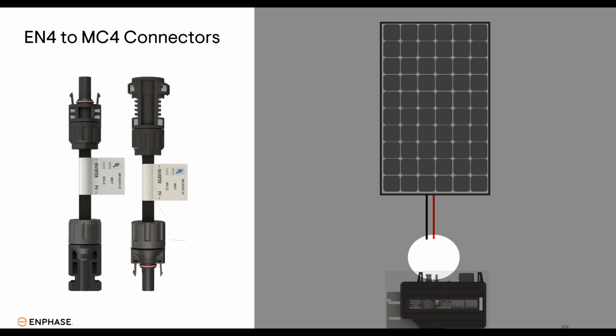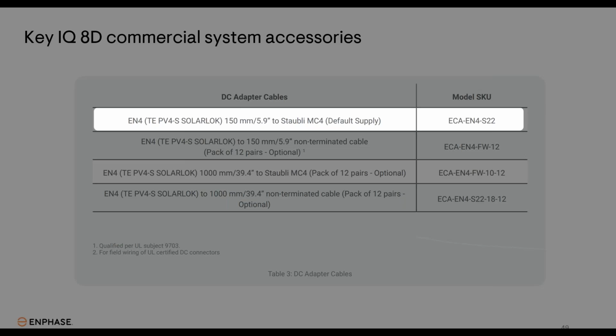It is important to understand that there's one side that has to be plugged into the microinverter and one side that will be plugged into your solar module if your solar module has MC4 connectors on it. So each EN4 to MC4 adapter is clearly labeled with which side needs to be plugged into the inverter and which side needs to be plugged into the PV module. Like I mentioned, that EN4 to MC4 adapter comes with each microinverter. So inside the box of 12 microinverters, there are 24 EN4 to MC4 adapters that are included. Those adapters are 5.9 inches long.